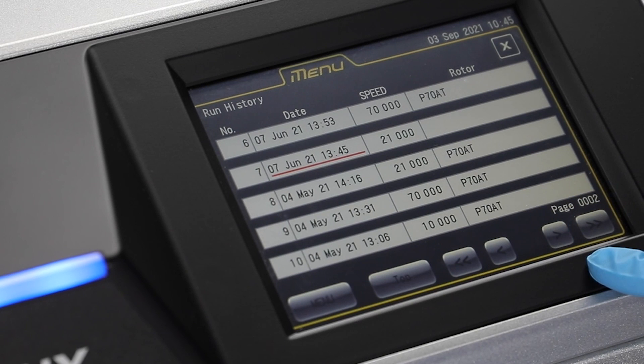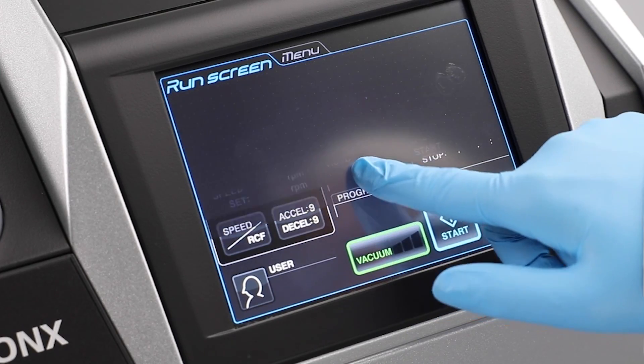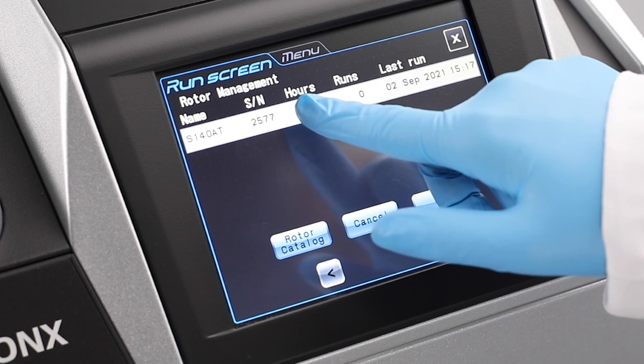In the pharmaceutical sector, the HIMAC machines record run parameters stored on the rotor. From a regulatory perspective, that can be quite important if the equipment is subject to audit from an outside regulator. From a safety perspective, it's important because typically in the pharmaceutical sector there will be no risk and no compromises made.